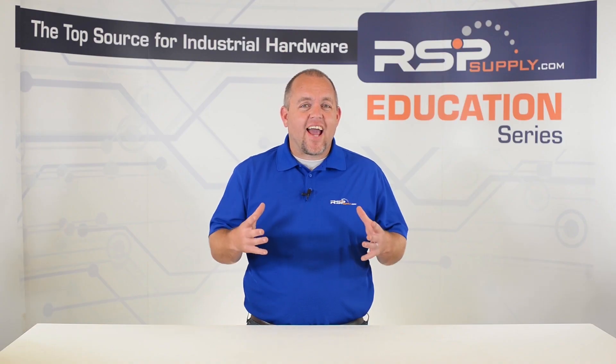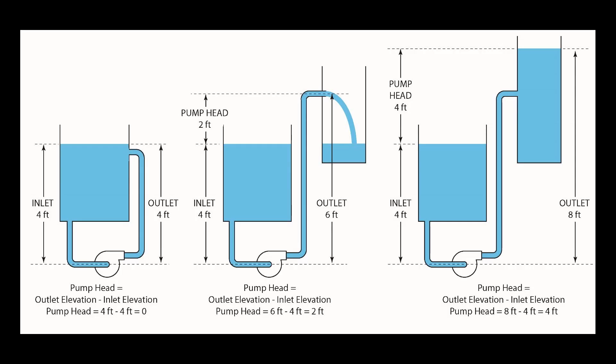Head is the height at which a pump can raise water or a type of fluid upward. Connect a tube or pipe to the discharge end of a pump and measure the height at which the pump can raise that fluid — this is the maximum head of that pump. This measurement can be done in feet, meters, inches, or any other metric used for length.